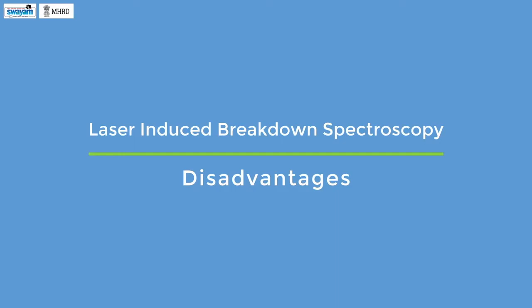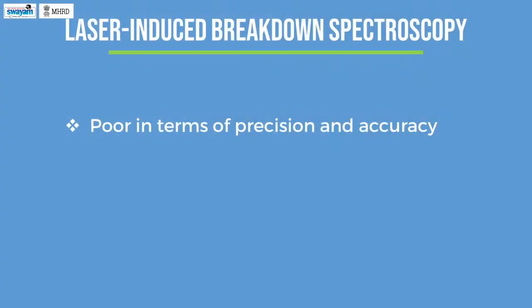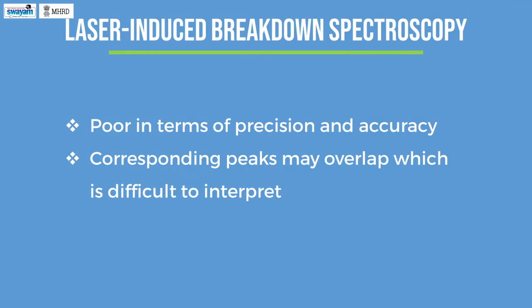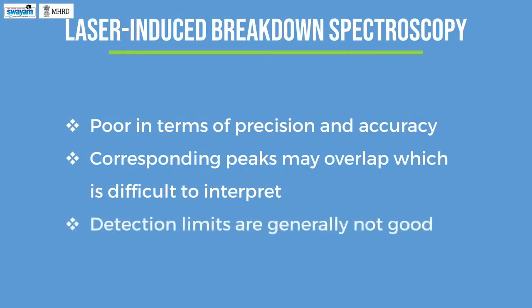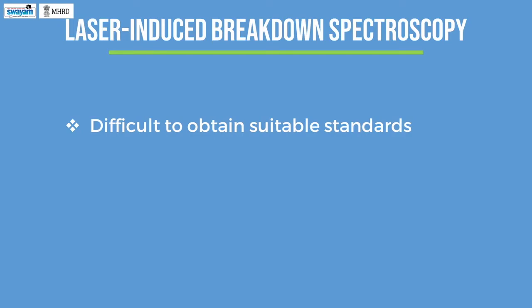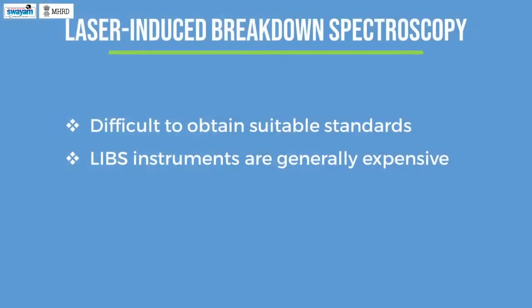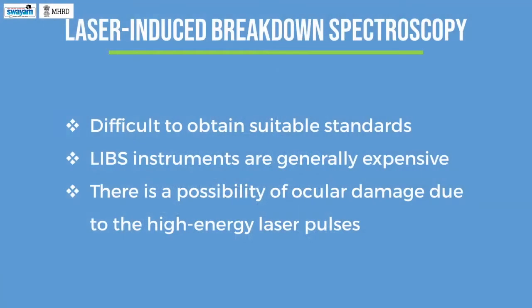Disadvantages of LIBS: LIBS analysis is poor in terms of precision and accuracy. A typical LIBS spectrum will have several peaks if the sample contains several elements, and the corresponding peaks may overlap, which is difficult to interpret easily. Detection limits are generally not as good as compared to ICP-AES techniques. Sometimes it is difficult to obtain suitable standards, which are required for quantitative analysis. LIBS instruments are generally expensive, especially due to the laser source, though portable LIBS instruments are relatively cheaper. Over time, there is a possibility of ocular damage due to the high energy laser pulses.